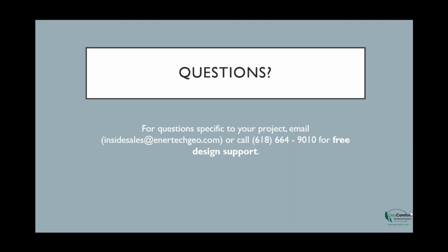Yeah, that's a good question. Obviously, we have a very technical person on the webinar. That's great. So in the past, if you used a specific water-to-water unit to do the domestic side, first of all, that water-to-water had to have a double-walled heat exchanger to meet code requirements, because you couldn't have potable water and refrigerant come in contact without a double-walled heat exchanger. But those heat pumps, if you look at the efficiencies that maintain 130 degrees, just number one, they weren't very good. They're not variable speed. They were a fixed capacity, usually around a 1.5 to a 2 ton capacity, and they were independent of the heating and cooling system. This particular product uses an indirect water heater, so we have a double wall isolation from the refrigerant to the potable water.